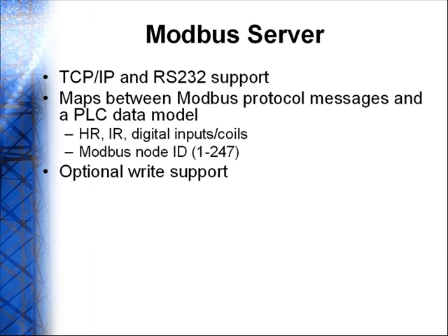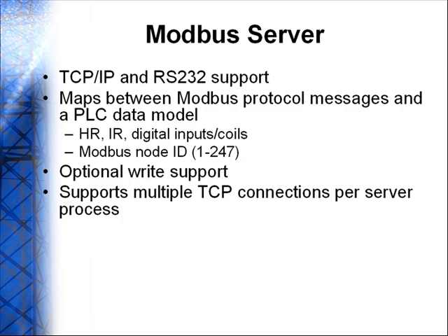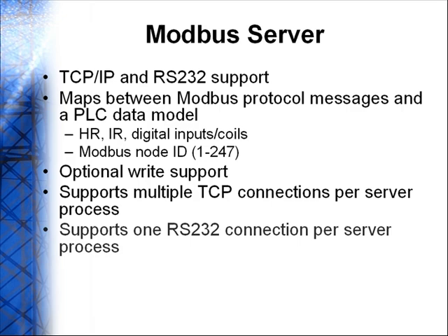Say you have station 1, station 2, station 3 in one driver, it'll assume those are Modbus IDs 1, 2 and 3. That's the default, so you don't have to specify anything else. But if you have multiple prefixes with different numeric suffixes, you can use command line support to map a particular Modbus station address to a particular station within any PLC model driver that's running on MacroView.